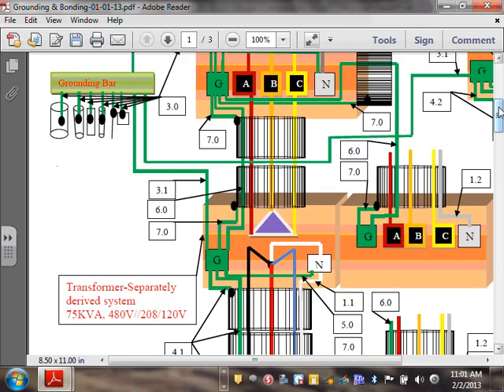Then, if your system is 480/277, you have to bond slightly differently, either by having proper fittings that tie to the panel, or a wedge that you install to bond the pipe. It's 480/277. If it's 208/120, it's not a big deal. That's for the equipment bonding the pipe for the equipment. Any comments, guys? Any questions about this sub panel?